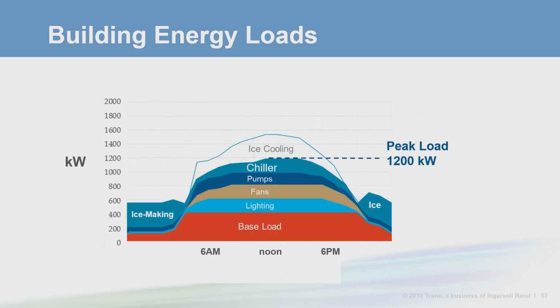By adding thermal storage, you can run the chillers at night when the electrical load is low and charge the storage tanks. That stored thermal energy can then be deployed during the daytime during peak loads to reduce the peak demand. In this example, the demand was reduced by 300 kilowatts and the customer's load factor increased significantly.